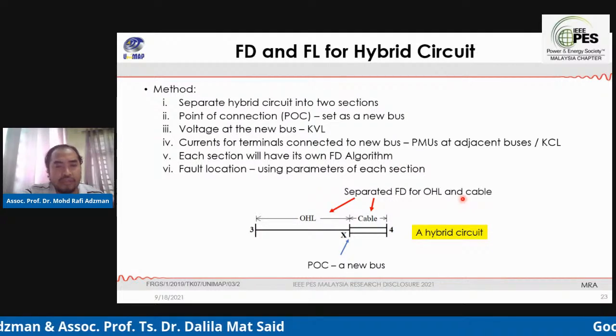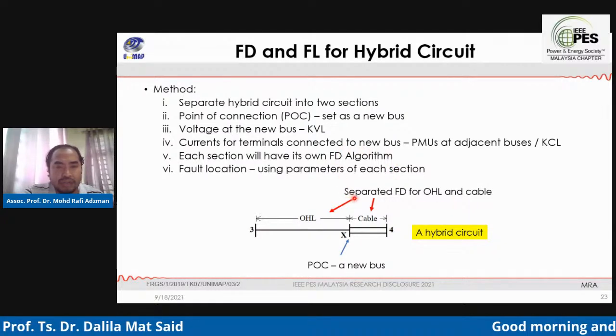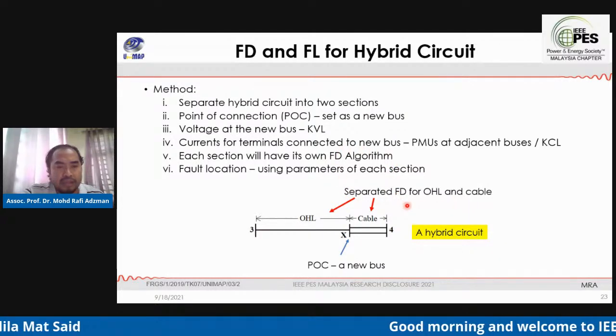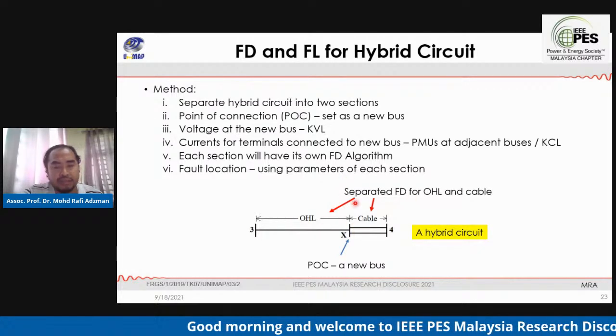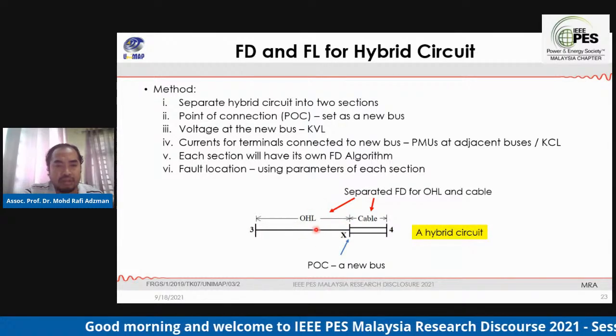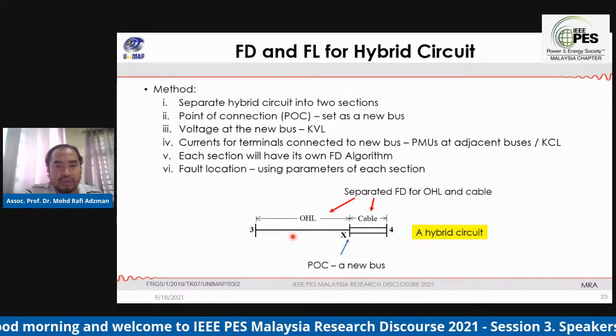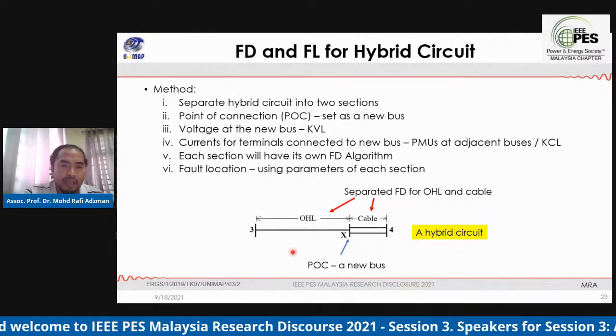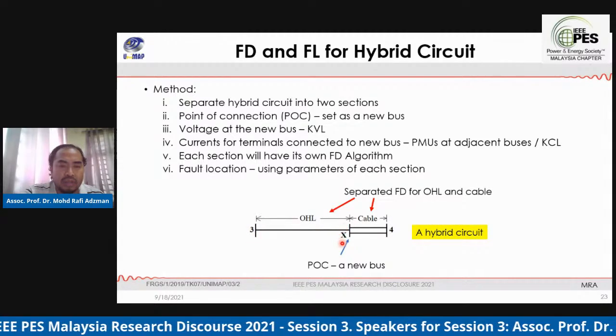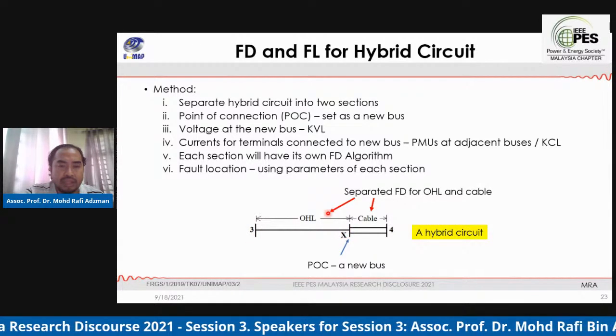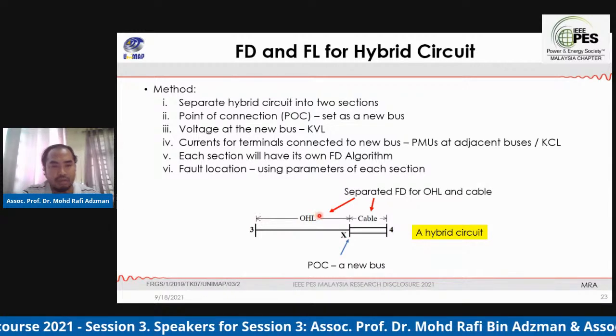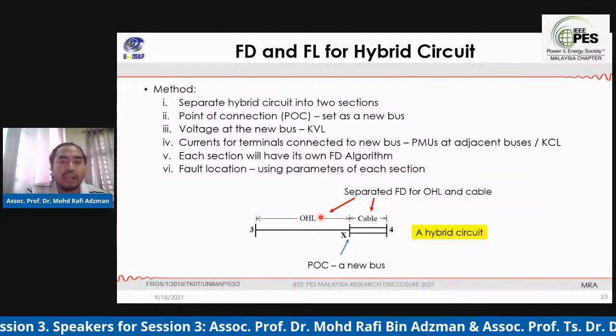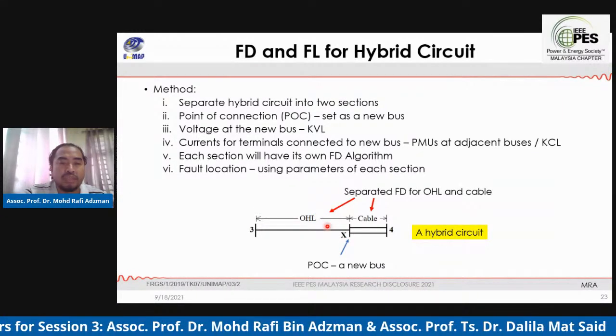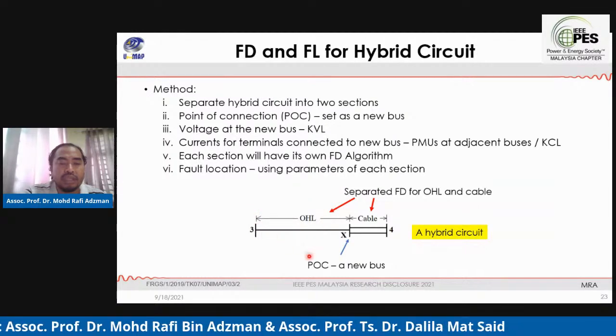Each section has its own fault detection algorithm, and the fault location uses the parameters of each line. For example, when the fault is located in this part from bus 3 to X, the new bus, we use the overhead line parameters to estimate the fault location in this line.